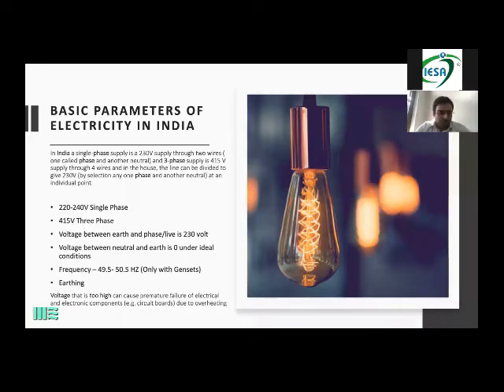The time these parameters are not met, if your voltage is higher or under this range, so 415 to 440 normal voltages, if your voltage is up or if it is down, then you should not start your electrical system, because it is bad for the equipment. Something can go wrong on site also. Over here, I've written that when the voltage is too high, it can cause premature failure of electrical or electronic components, that is the circuit boards, due to overheating.